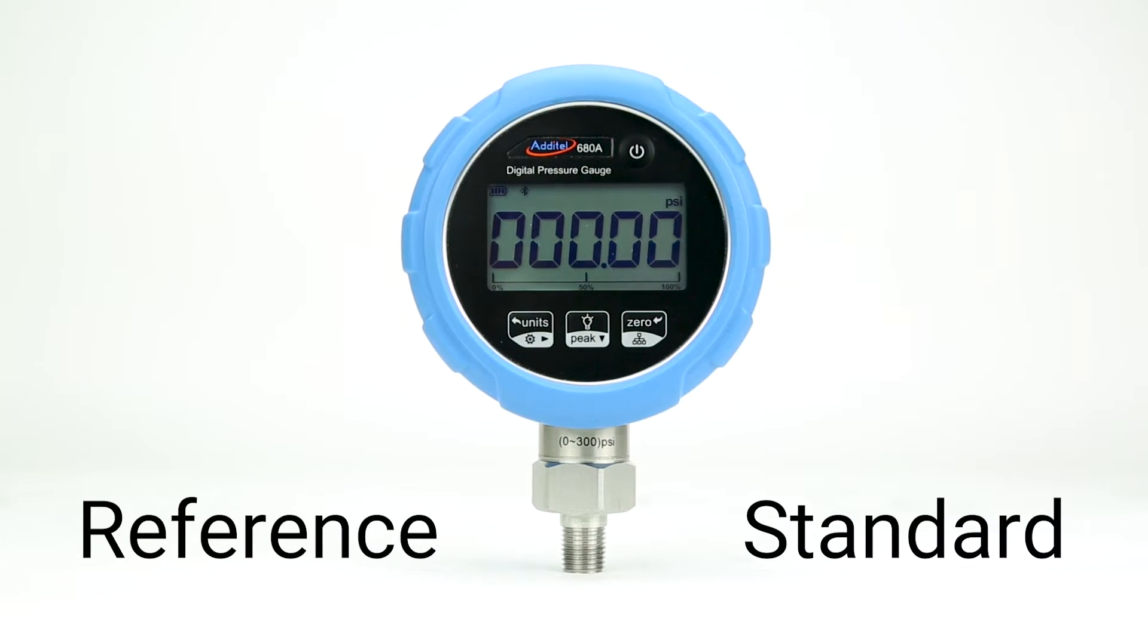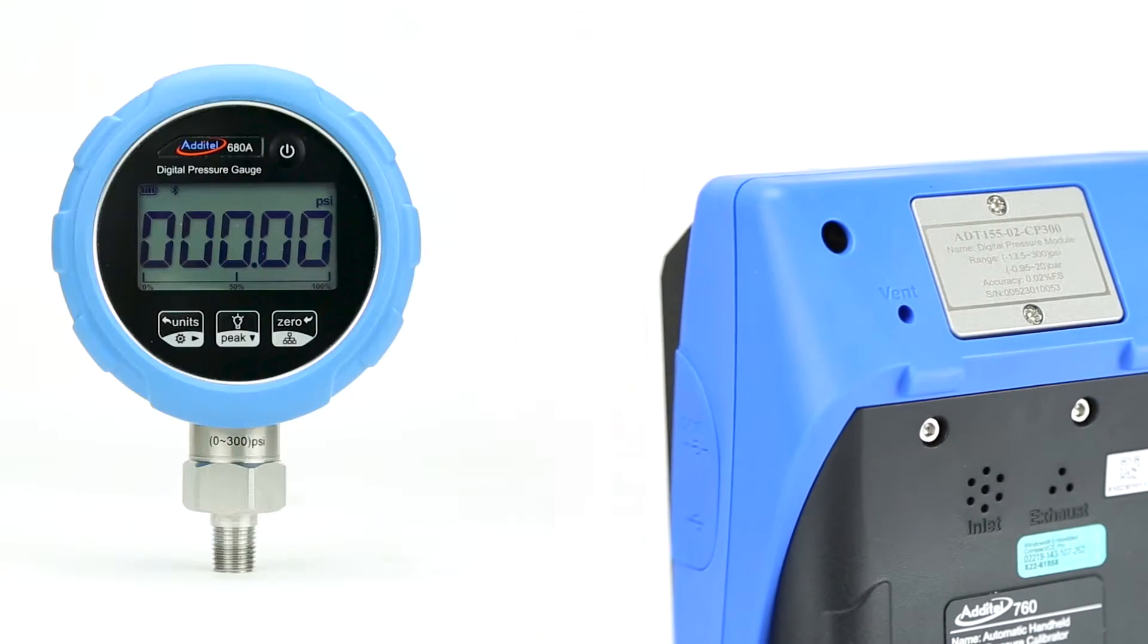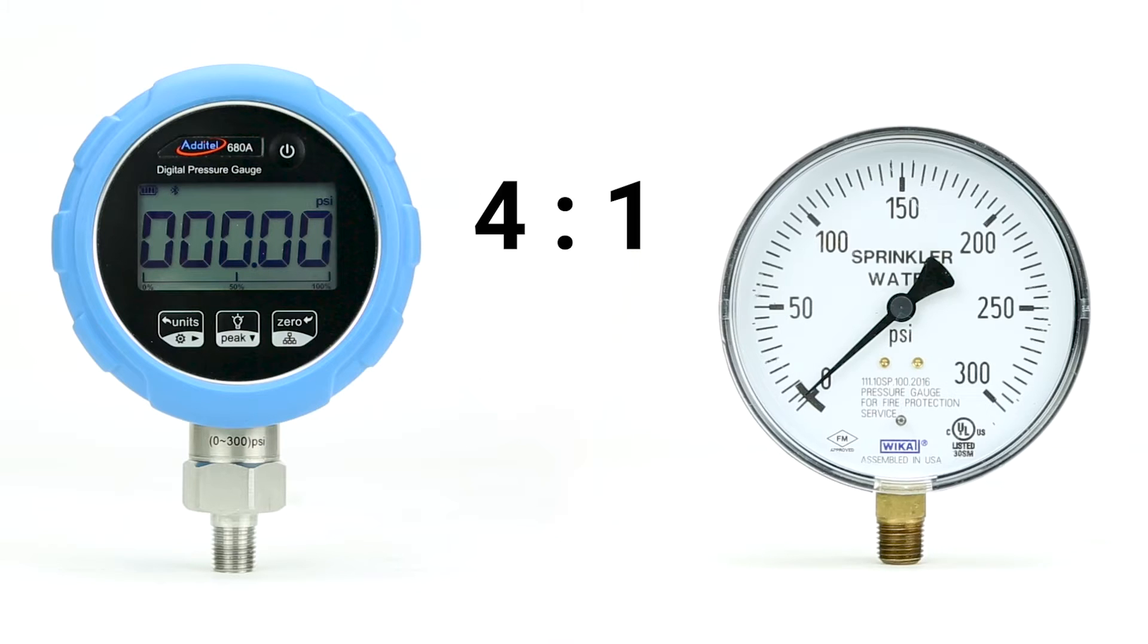This could be another gauge module or even a sensor within the pressure controlling device. A general rule of thumb is to have the reference be at least four times as accurate as the DUT, also known as a 4:1 test accuracy ratio, or sometimes referred to as a test uncertainty ratio.